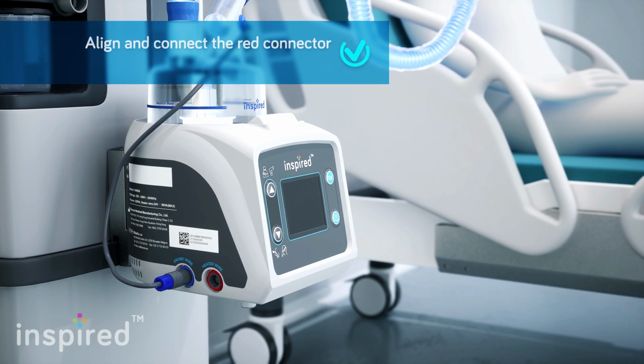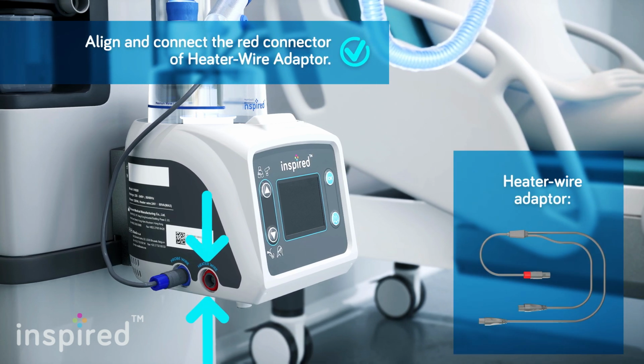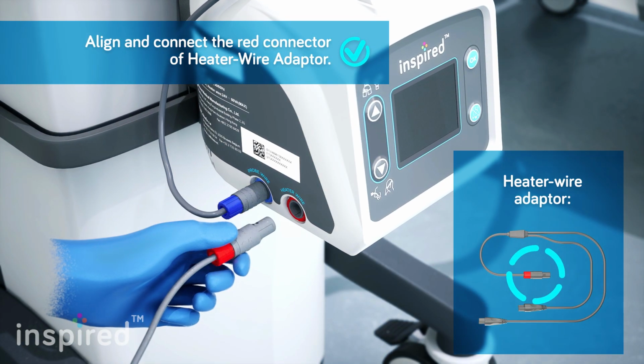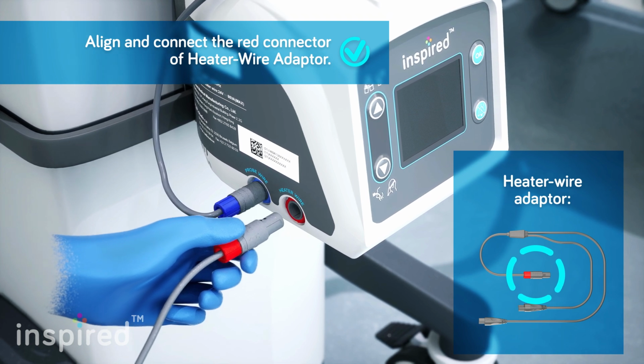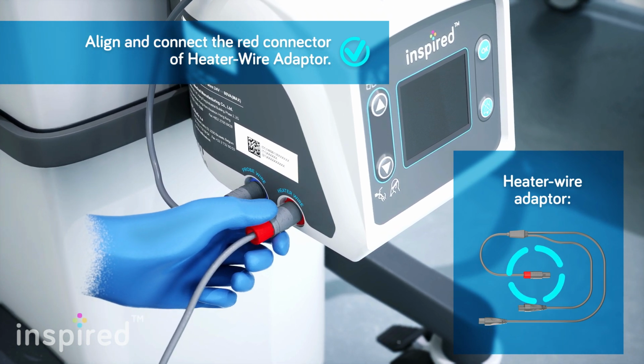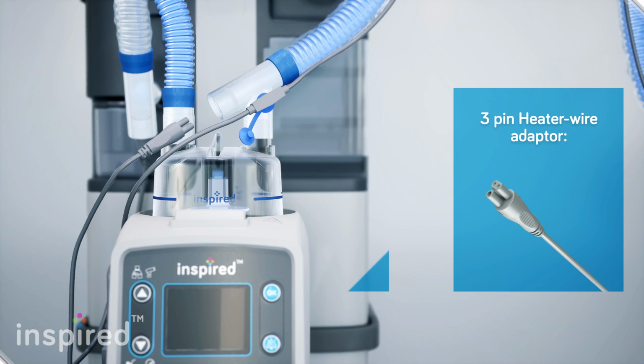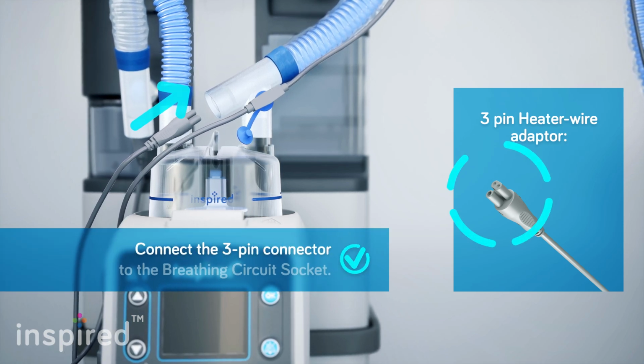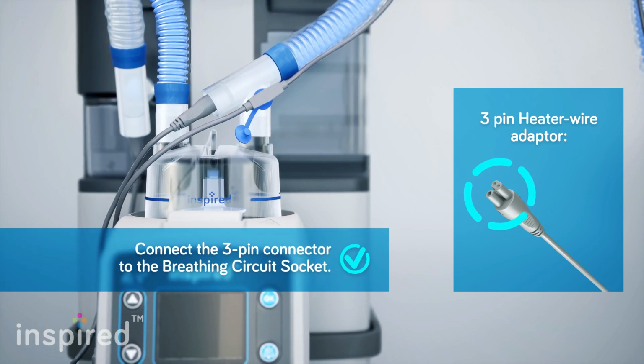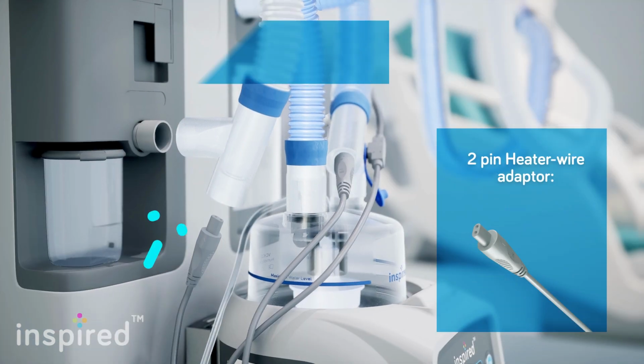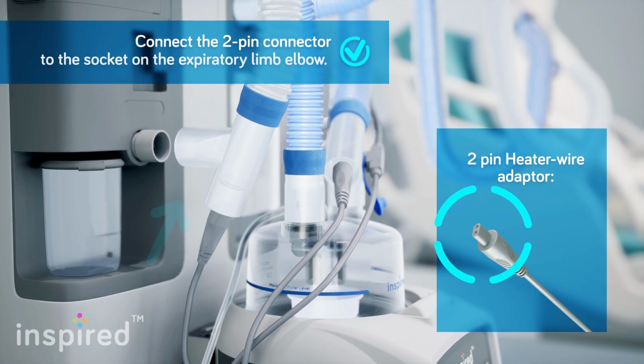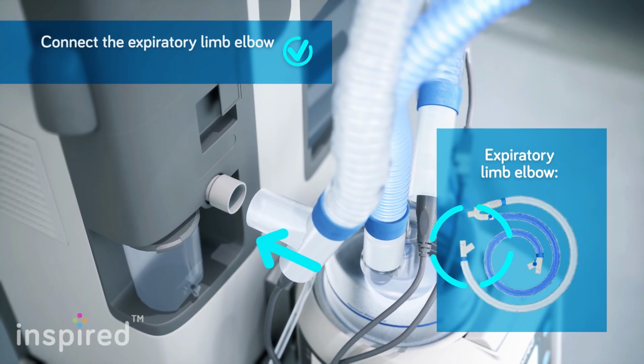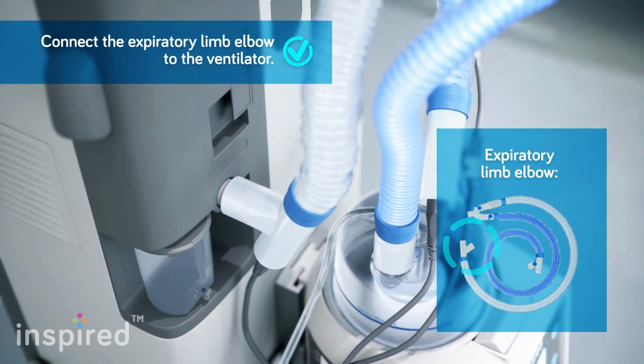Align and connect the red connector of the heater wire adapter into the red socket found on the left side of the device. The connection is secure when there is a click sound. Connect the 3-pin connector to the breathing circuit socket on the inspiratory limb. Connect the 2-pin connector to the socket on the expiratory limb elbow. Connect the expiratory limb elbow to the ventilator. Dual heated wire breathing circuit setup is done.